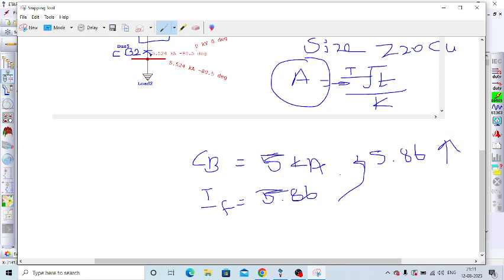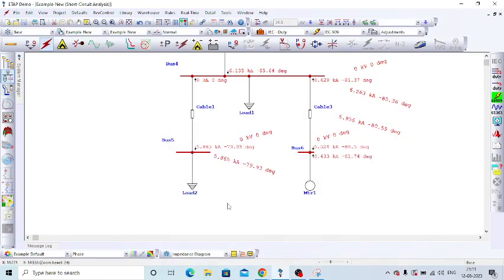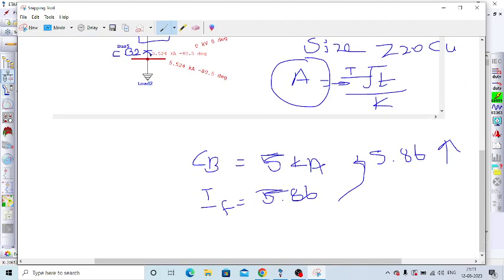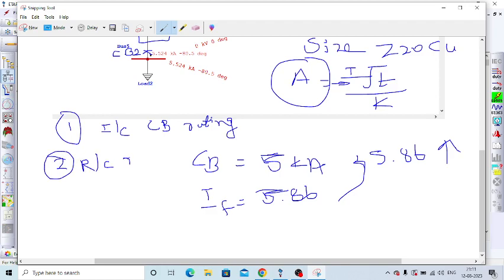But in this location, compared to the circuit breaker rating, the fault current is high, so we don't have much option. The first option is to increase the rating of the circuit breaker to 5.86 or a higher value. So option 1 is to increase the circuit breaker rating. The second option is to reduce the fault current.